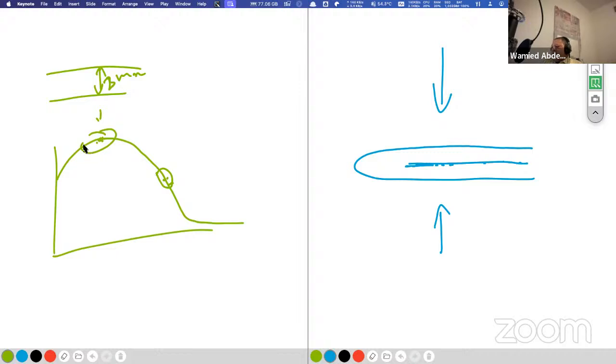So the best suggestion is actually to use a smaller dosimeter. So use a dosimeter that has 1 millimeter. Recombination is still going to happen there, but at least we are reducing it a lot because the volume is now smaller, so the ions are collected faster. We're not giving them space to interact with more ions for recombination. So we shifted. We had to use a 1 millimeter Markus chamber. We could use, for example, a pinpoint cylindrical chamber.